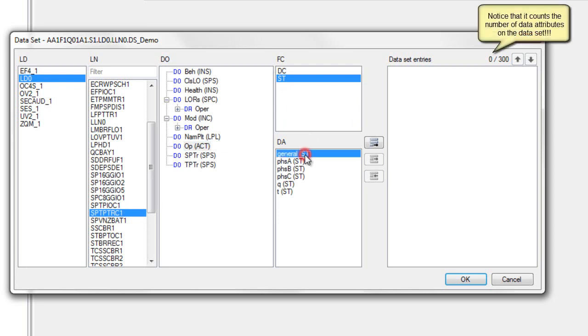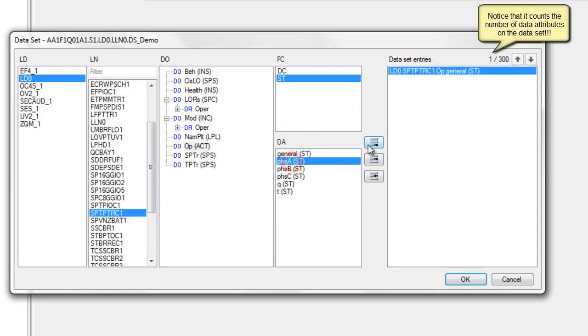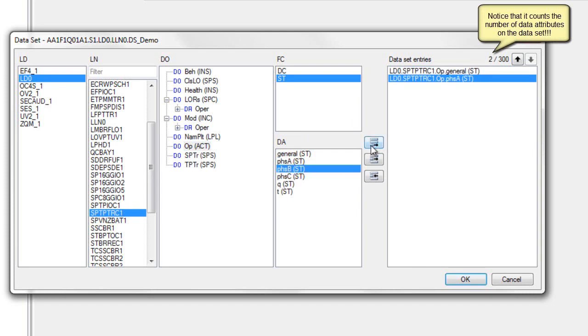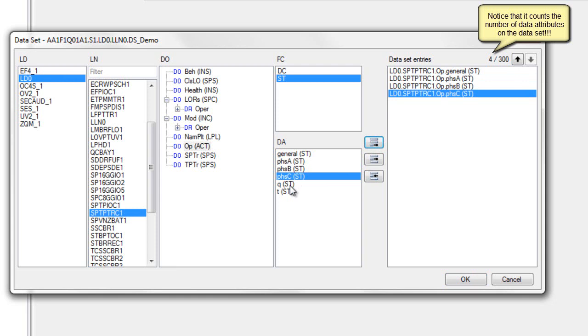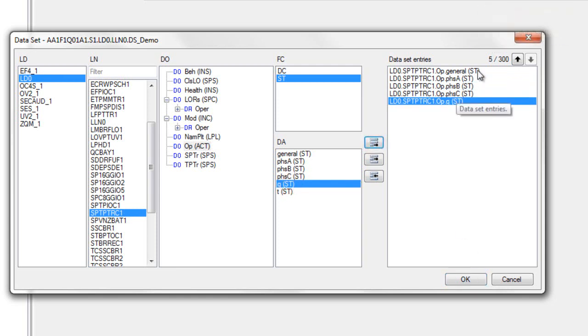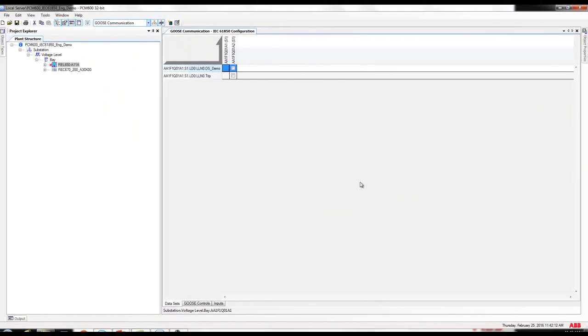Click general, add. Then phase A, add. Phase B, add. Phase C, and so on. Do not forget to include the quality. Now we have the general signal, phases A through C, and the quality. Click OK, and now we have created the dataset coming from the REL650 with the data attributes that we want to publish.